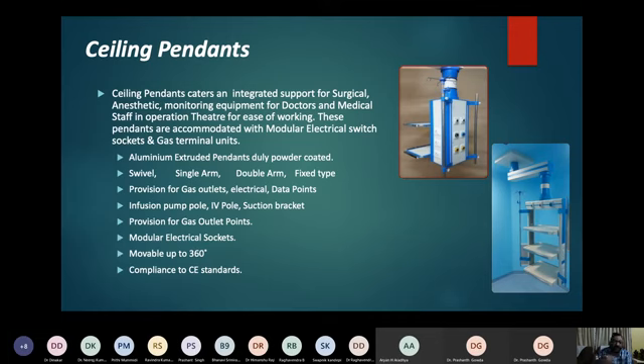In the anesthesia pendant, you can connect to the gas outlet, the electrical data points, depending on how many outlets and electrical points you need. All this you can design, customize and fix it over there. Also the same way you can put the electrical socket. It can be 360-degree movable. In double arm, you can rotate it 360 degrees, and pneumatically you can stop it anywhere you need to fix it. Sometimes it may rotate unintentionally, so pneumatically you can fix it, and there is a lock also, available nowadays in most pendants. This will be ISO, CE, sometimes FDA compliant, depending on the hospital choice.